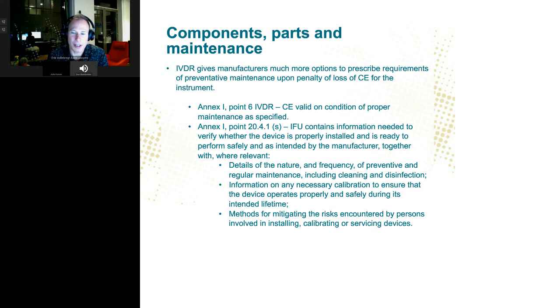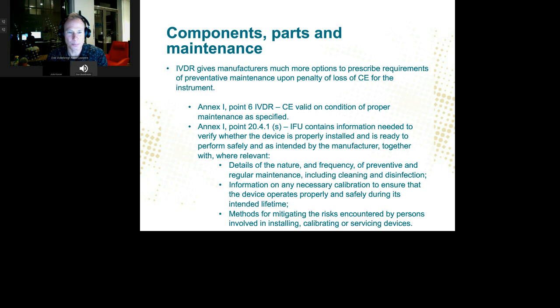What you should also understand is that the manufacturer of the instrument or the IVD has a lot more options to prescribe requirements for preventative maintenance under the IVDR. The IVDR says that the CE marking is valid on condition of proper maintenance as specified by the manufacturer. And the manufacturer has a lot of obligations on how to do this. But this also means that he can make it really difficult for the aftermarket, for other parties than the OEM, to provide these devices. And that's something, if you're in that kind of market, you should be aware of.